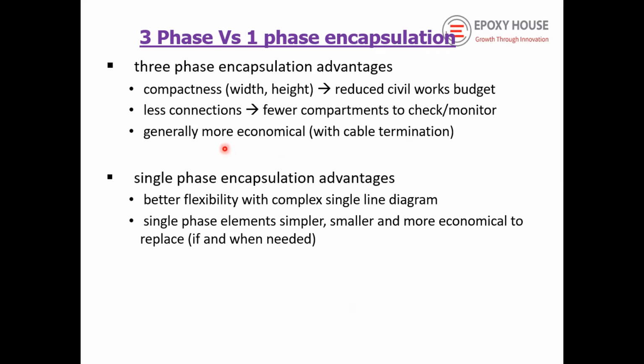Single-phase encapsulation has the advantage of better flexibility with a complex single line diagram. You can change anything easily. Single-phase elements are simpler, smaller, and more economical to replace in case of higher voltage ranges.